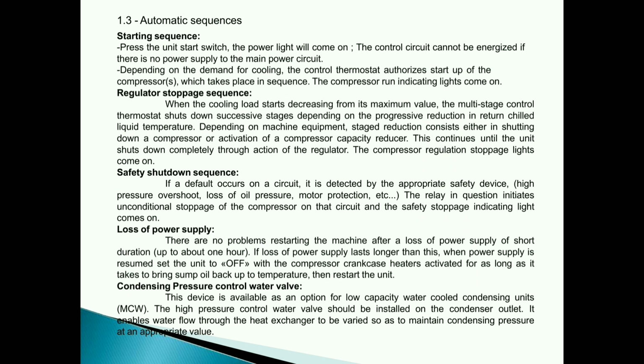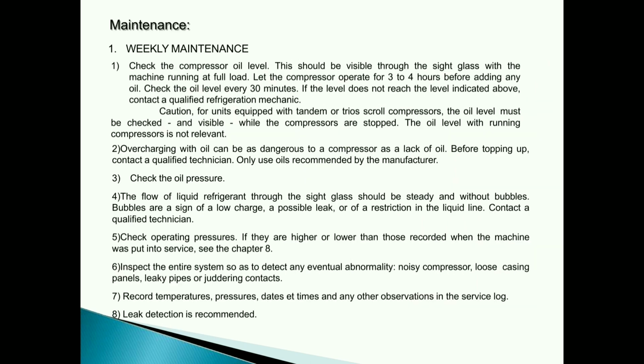This device is available as an option for low-capacity water-cooled condensing units, MCW. The high pressure control water valve should be installed on the condenser outlet. It enables water flow through the heat exchanger to be varied so as to maintain condensing pressure at an appropriate value. Maintenance. 1.0 Weekly maintenance.